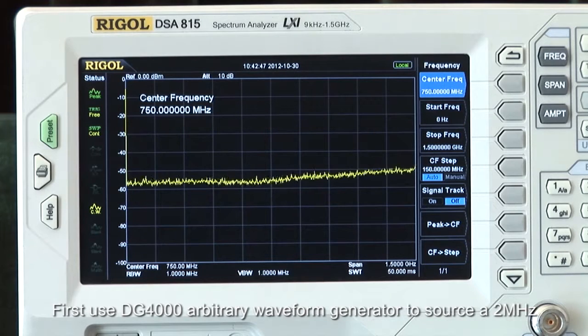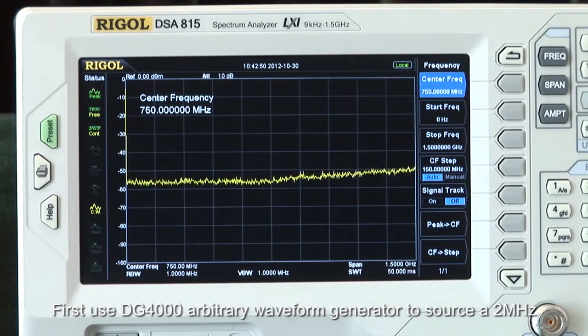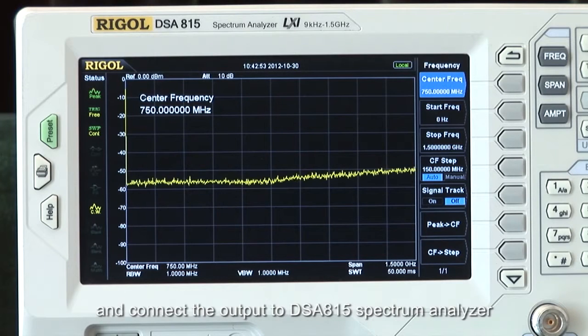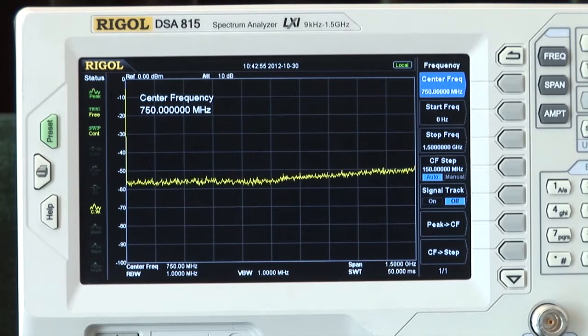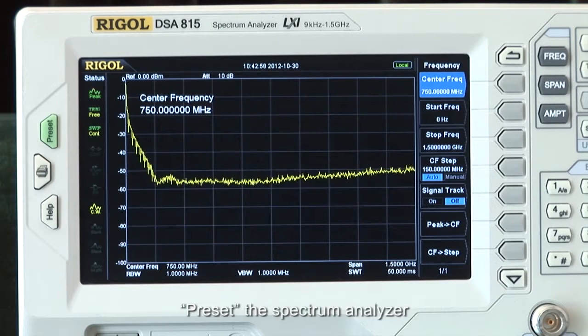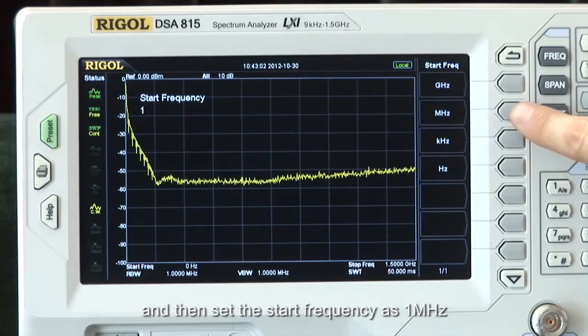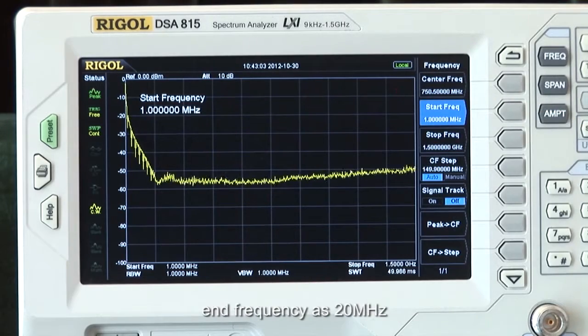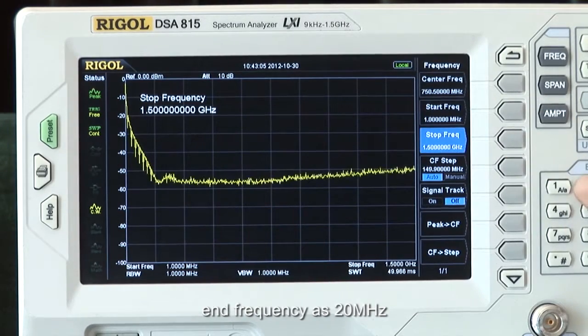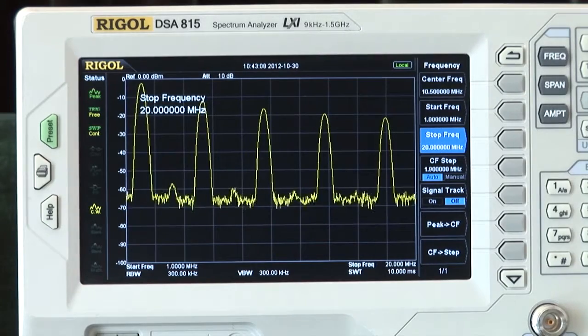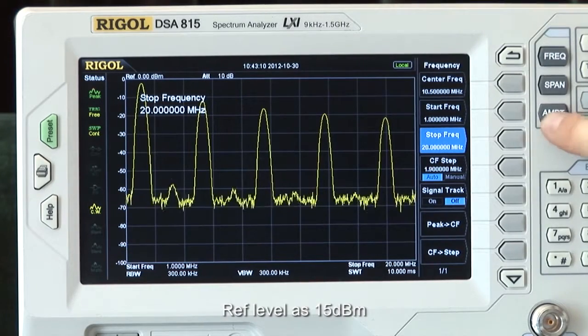First, use the DG4000 arbitrary waveform generator to source a 2 MHz, 0 dBm square waveform, then connect the output to the DSA815 spectrum analyzer. Preset the spectrum analyzer, and then set the start frequency to 1 MHz, the end frequency to 20 MHz, and the reference level to 15 dBm.